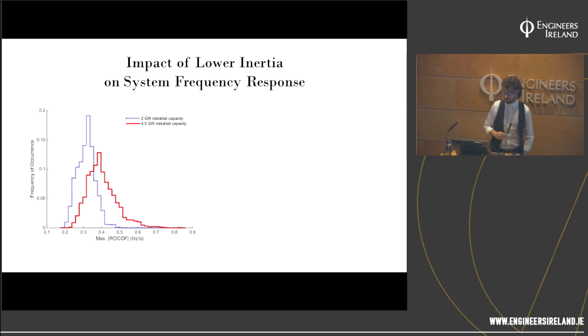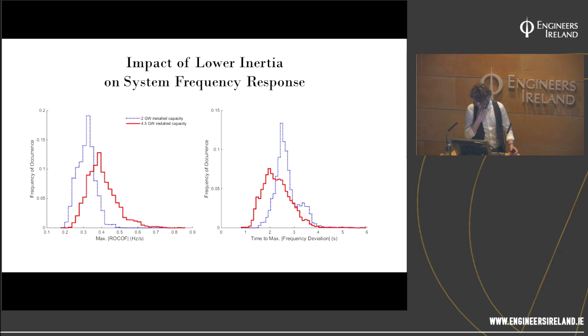The first is the rate of change of frequency. This is a probability distribution function of what your rate of change of frequency will be if you lose the largest generator on your system for every hour in the year. All I want you to get here is that as the wind penetration increases, that curve is pushed to the right, to more extreme rates of change of frequency. The other thing it has a direct impact on is the time to maximum frequency deviation. Because we're falling faster, we're hitting our minimum frequency in a shorter time frame.